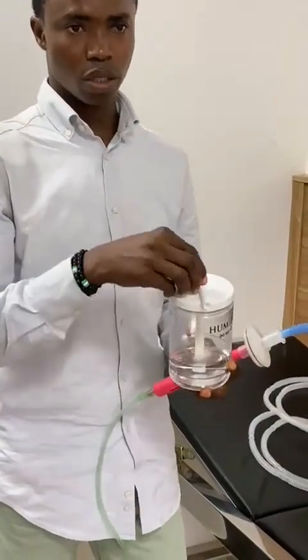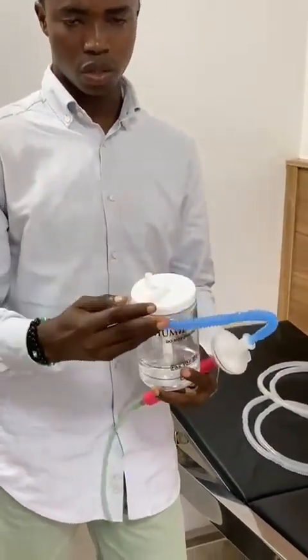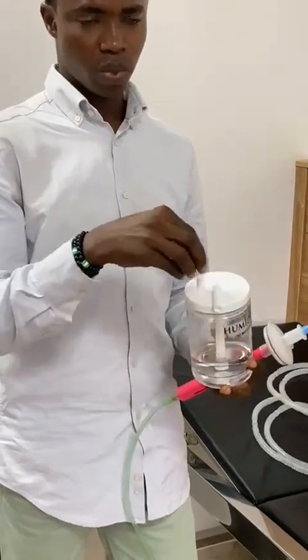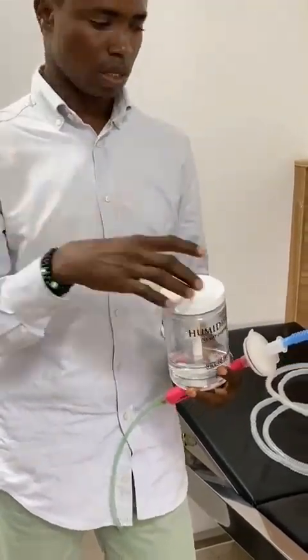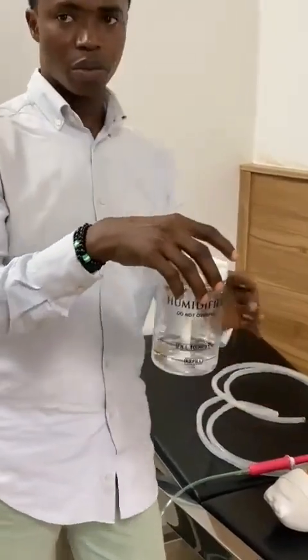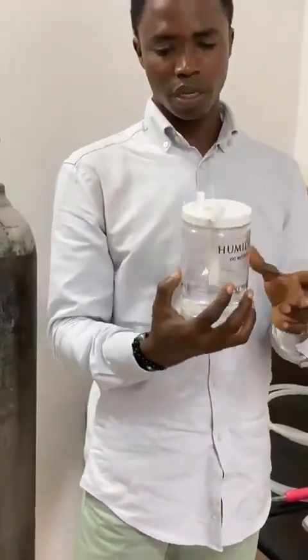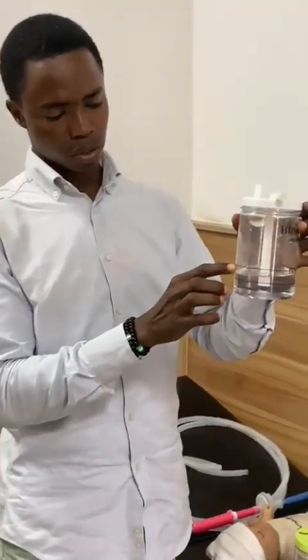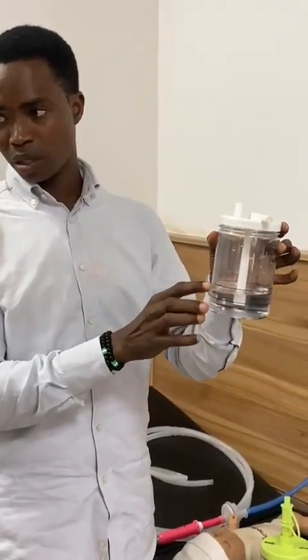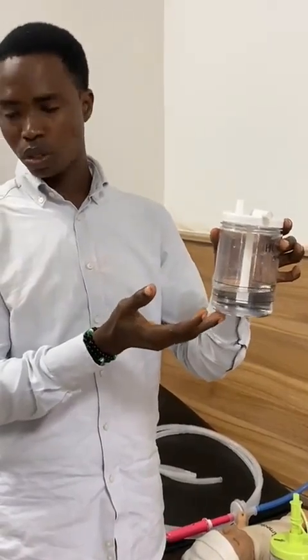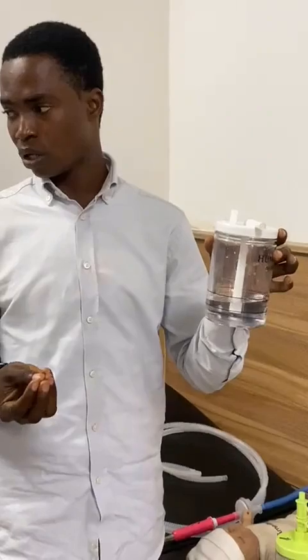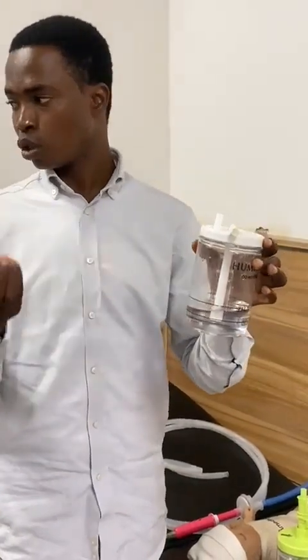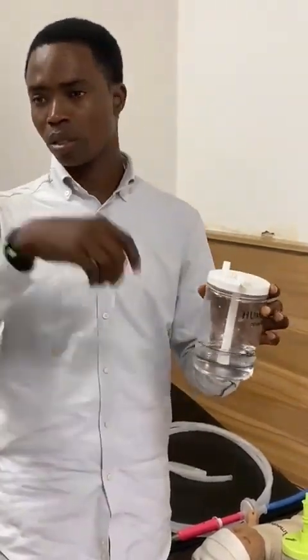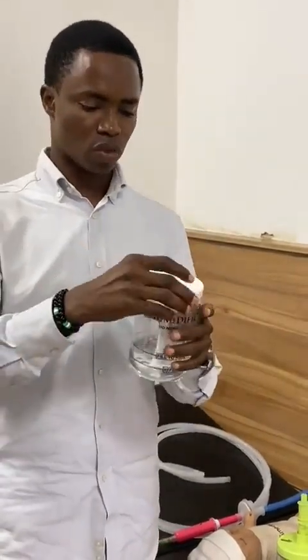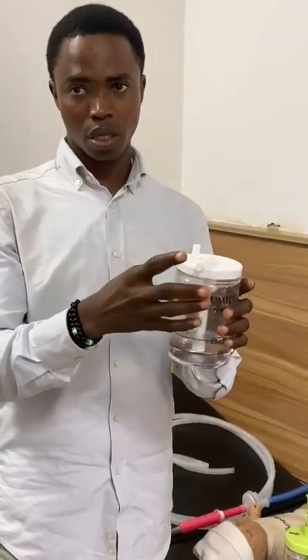This inlet is the one that connects to the oxygen source, while this one is the one that goes to the patient. We fill this humidifying bottle with water. It has a calibration between the minimum and the maximum level. If it's too low, there won't be efficient humidification, and if it's too high, there will be too much humidification and water can go through the tubings to the patient. That's why. Also ensure that it's properly locked so that there's no leakage. If there's a leakage, pressure will be lost.